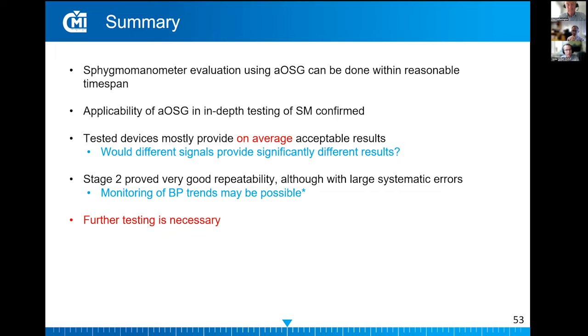precaution taken into account. Of course, further testing of this sphygmomanometer testing is necessary, since within this testing we only tested devices of, I would say, lower price range, because the price of these devices was between 15 and approximately 100 euros. I dare to say that if we test devices that are intended for use in clinical environments, which are of course much more expensive, the results could be significantly different. Yet a question that also remains open is, if we would use different signals from the vast database that is available, how different the signals would be. That is also a question to be answered by future testing.